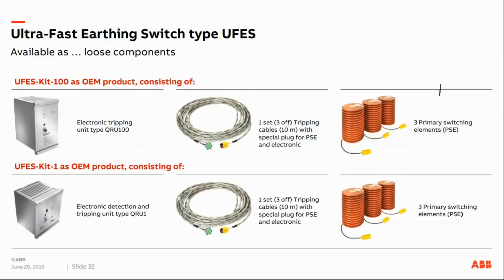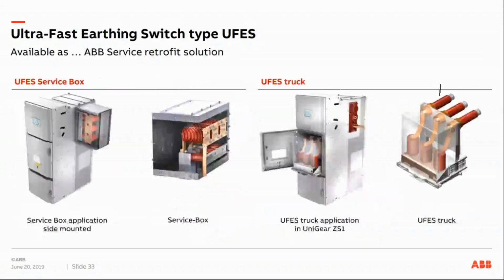Usually the UFES as loose components comes in a kit solution. This is a popular solution for OEMs. The UFES kit comes either with the QRU 100 or the QRU 1, always with one set of tripping cables and a set of primary switching elements. So particularly for older non-IAC qualified switchgear systems, the UFES allows the highest degree of protection for your equipment and operator safety. And we have a variety of solutions for retrofitting of existing switchgear systems, since there might not always be the option of upgrading or exchanging a complete system.